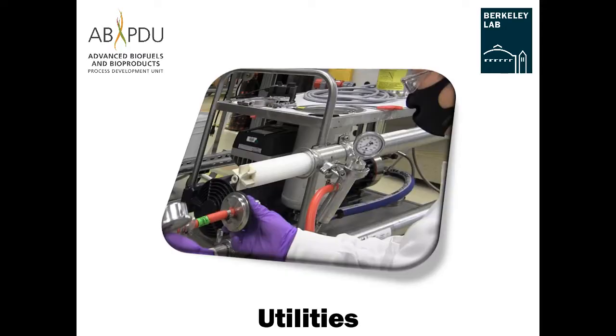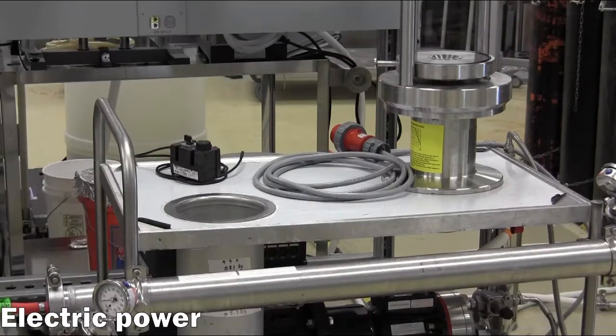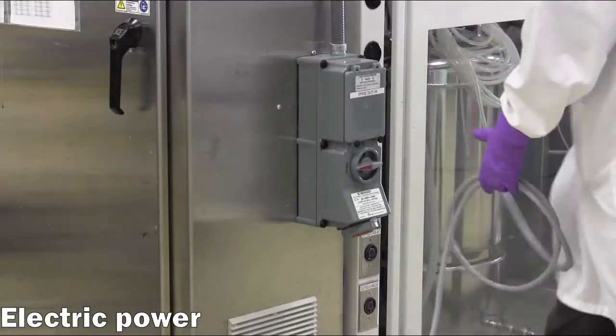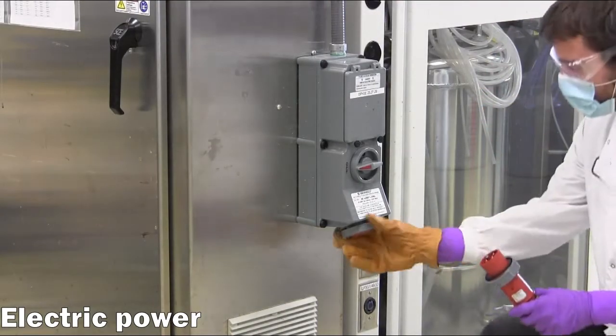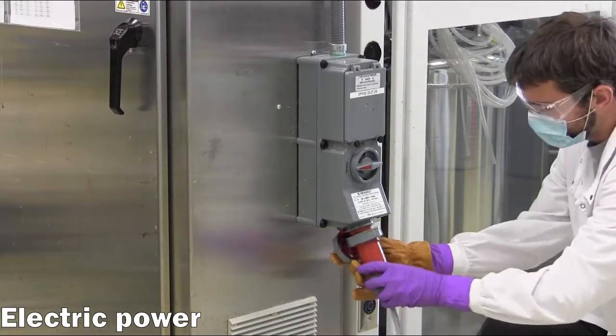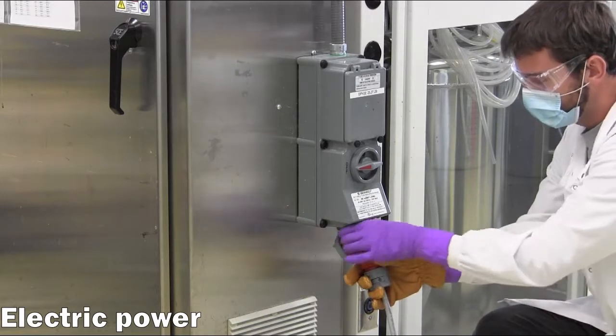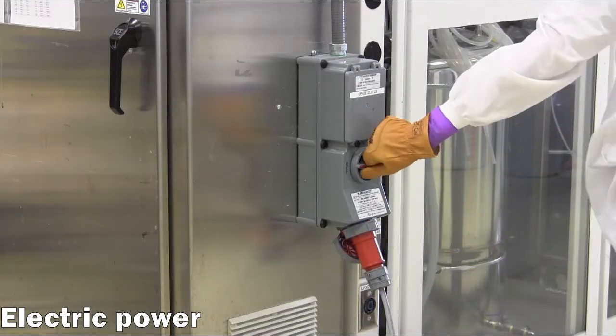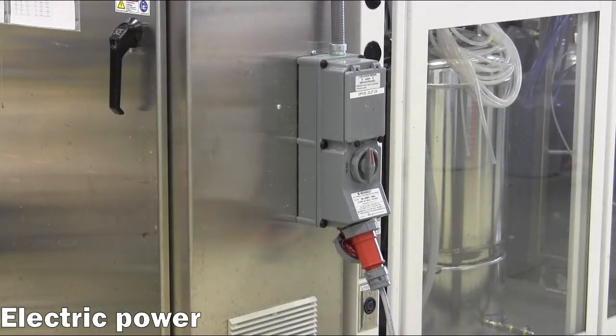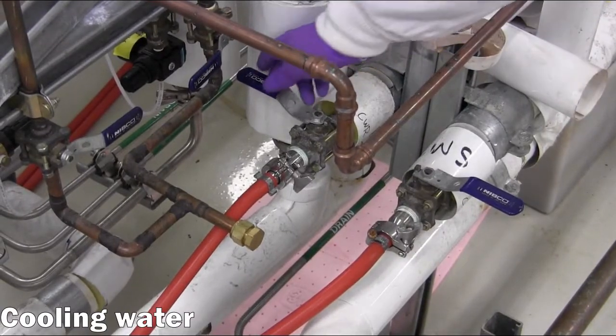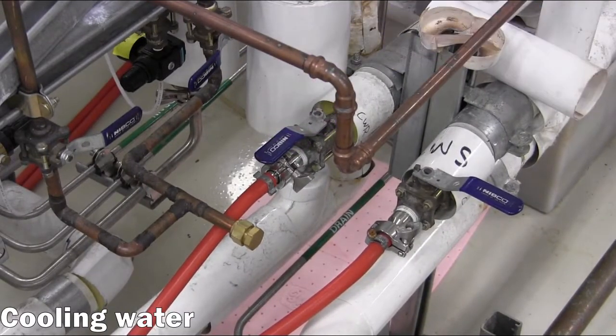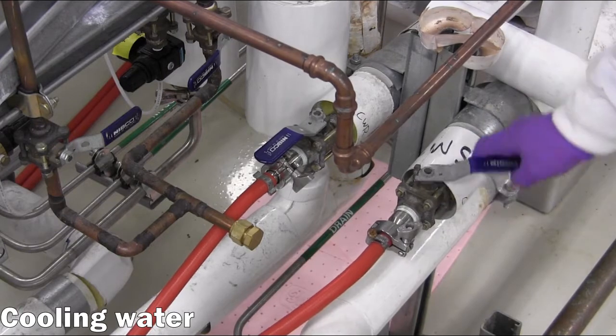Utilities. After donning leather gloves, the electrical cord may be connected to a 480-volt power source. The technician then steps to the side of the breaker box, looks away, and switches the breaker to the on position. Both valves for the chilled water supply and return are open to allow recirculation to the house system.